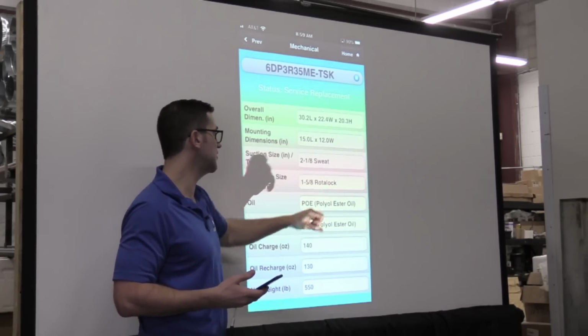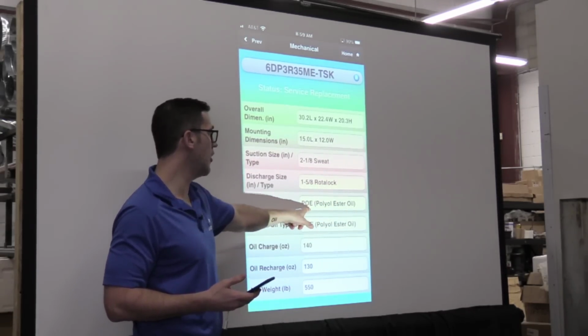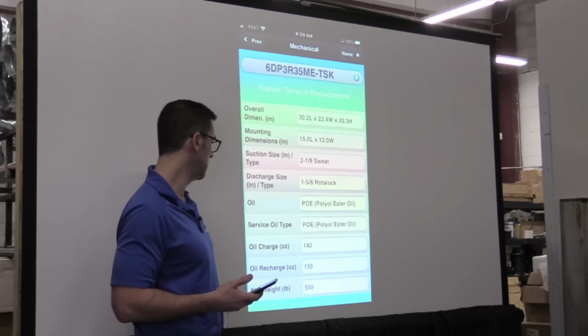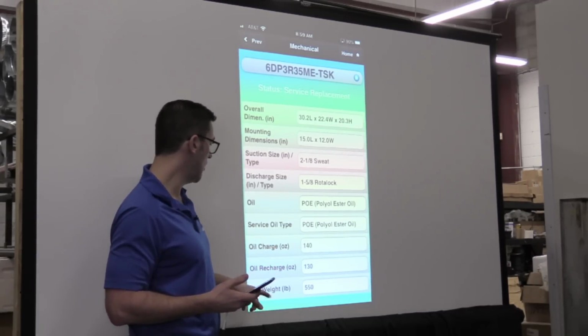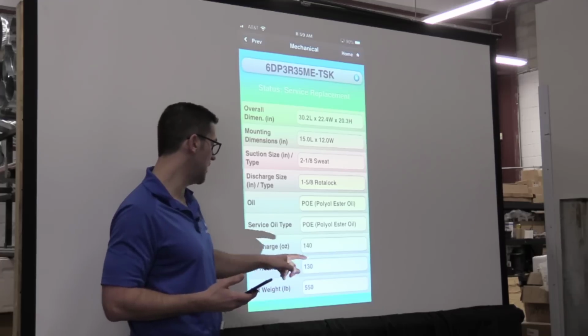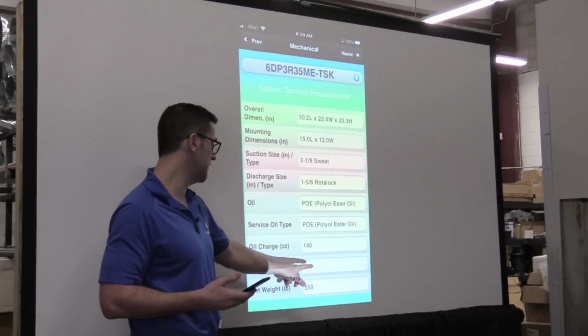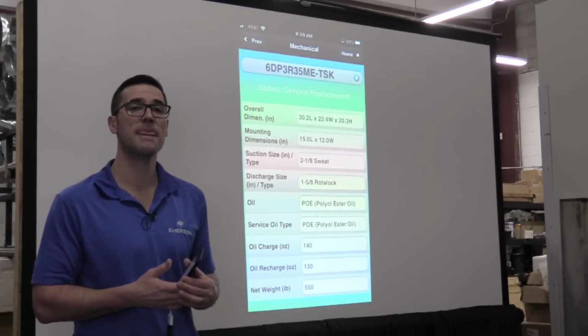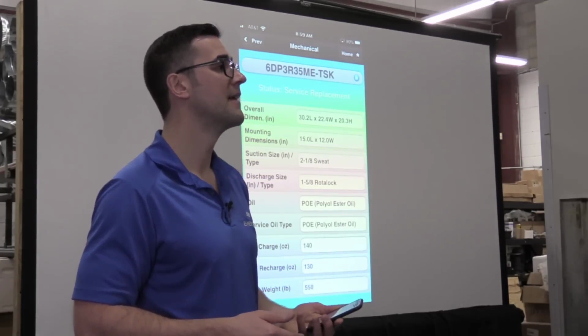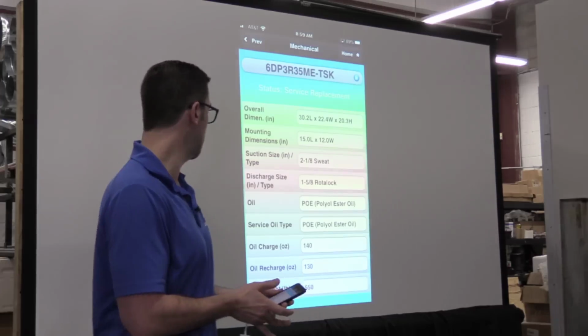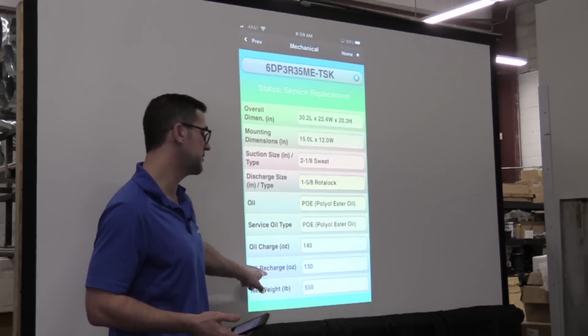So it tells you if you're going to sweat it in or it's a rotolock. Type of oil, polyol ester oil, right? Service oil, oil charge, and oil recharge. What do you think the difference is between oil charge and oil recharge? Can anyone tell me? 10 ounces may be left in the system. Attaboy, exactly. So this is an OEM compressor, new compressor. This is a service compressor.